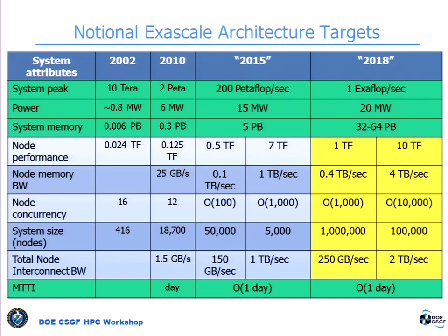If you look at that and you try and project out and think about it, some estimates for this 2018 system using conventional technology had a power usage between 100 and 400 megawatts. And I said that properly. It was 100 and 400 megawatts. If you just assume that most power for systems like these cost about $1 million per megawatt year, you would need at least $100 million just to keep the power on for the system if you use conventional technology. That's not sustainable and not practical in our current, well, in many environments.